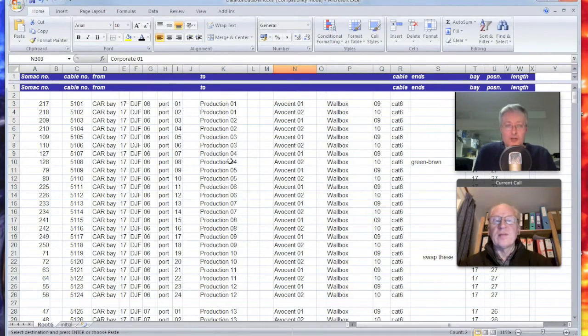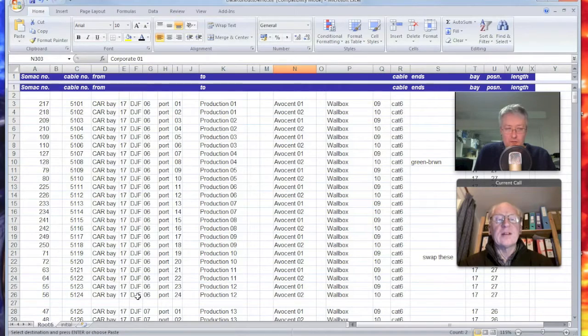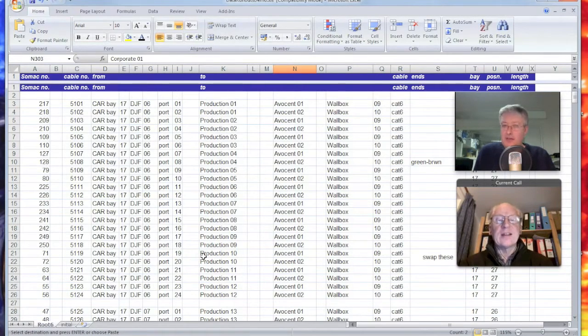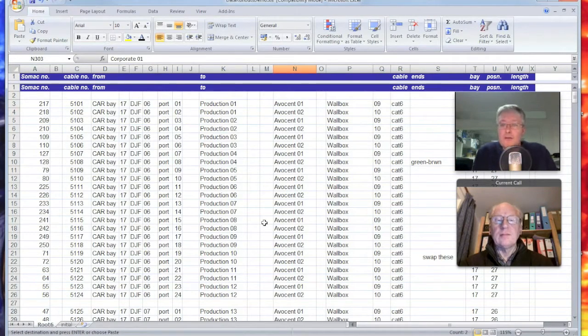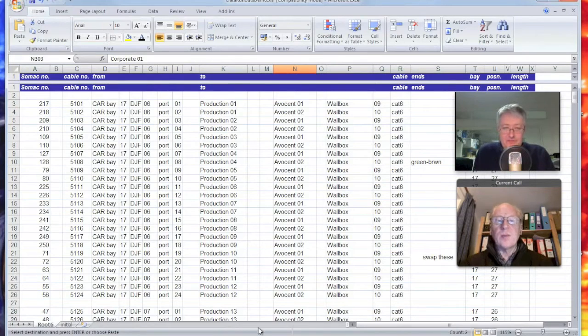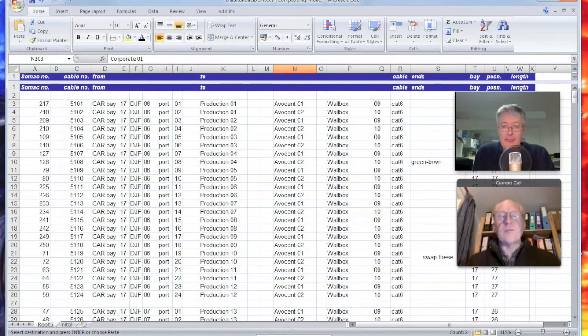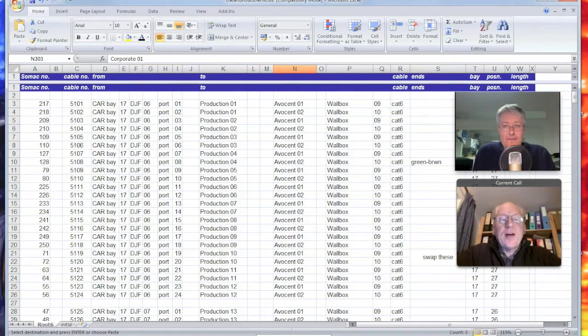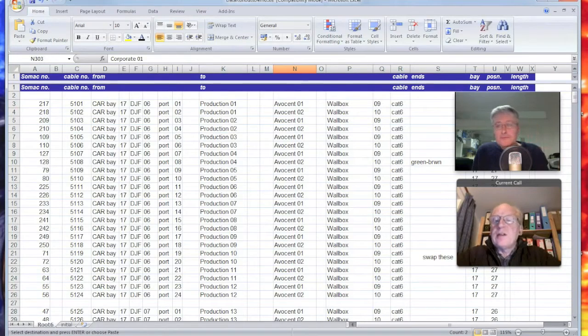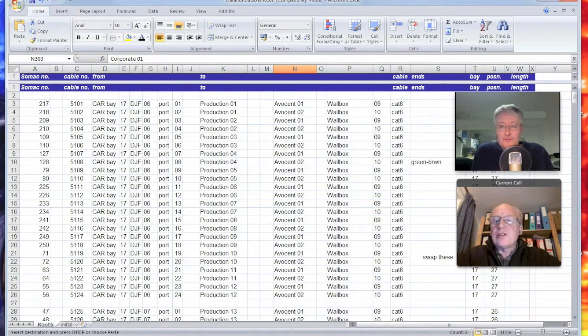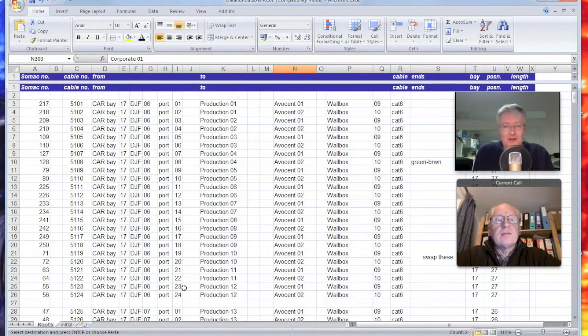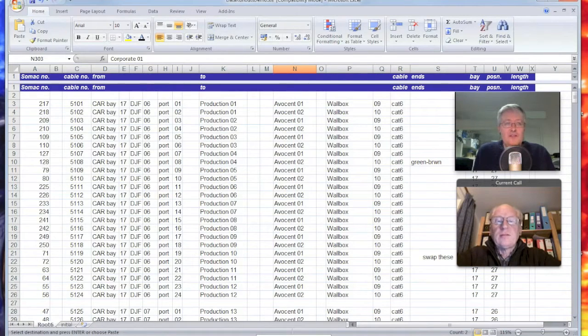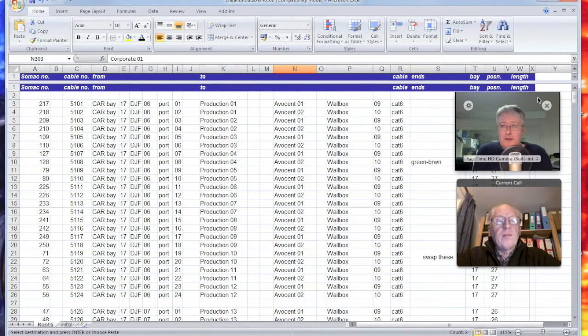So kind of a combination of sorting the spreadsheet to see if I've got any holes and dropping in new information, then resorting the spreadsheet is how I get from a very basic set of information to a very fully featured cable schedule that I can then give to the wireman. So the wireman can go through looking at the numbers he's got on the cables that have been given to him, replacing those with the proper numbers that we've agreed with the customer that are part of the facility-wide numbering system, and then how he's going to terminate that onto patch panels.